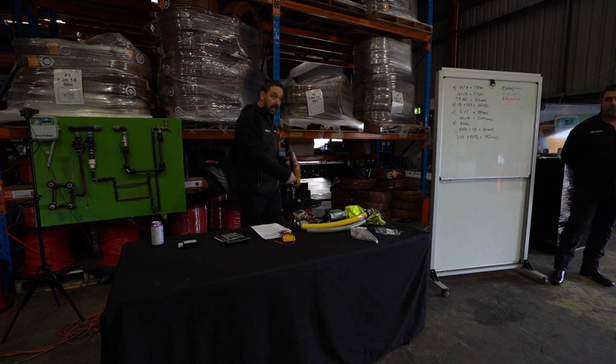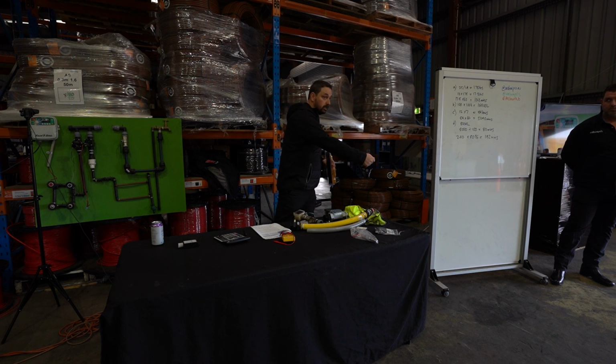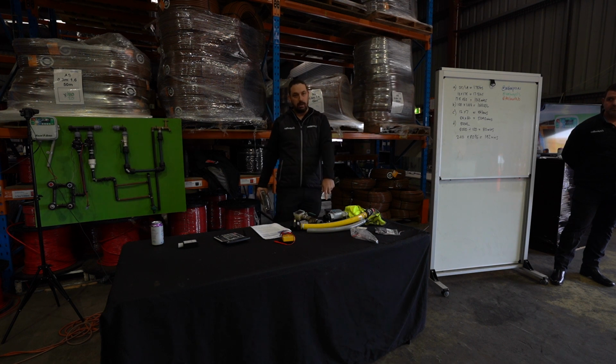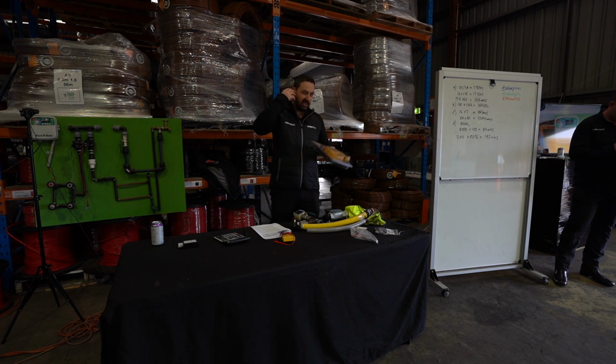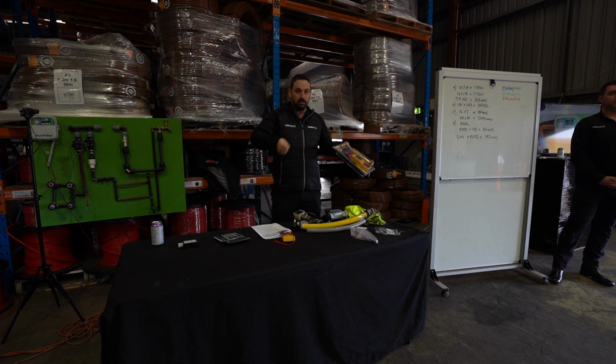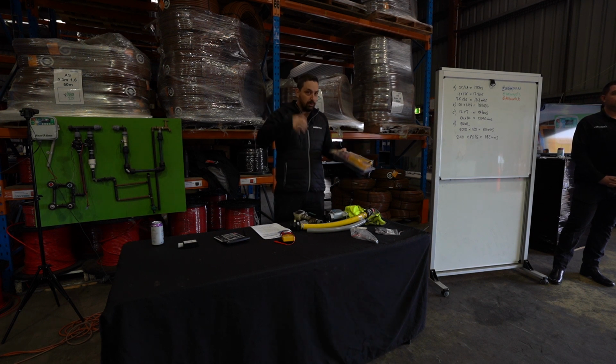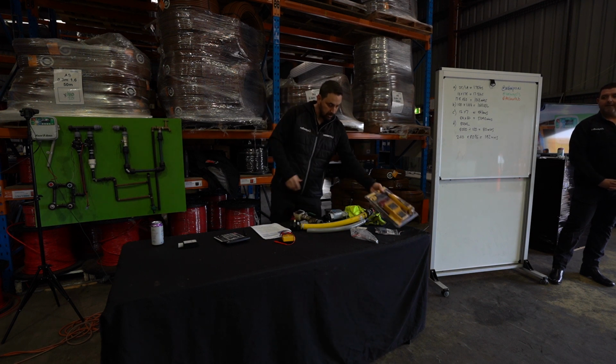and then I'd be able to walk along, and I would find the cable until I lost signal, because I might be dead out in an area, and then I'd come back and I'd find it, spray paint or dig a hole, and I'd know something's happened down here and there's a break in the line. And it can give you strength signals and all that sort of stuff, and you can get headphones with them, so if you're in a streetscape where there's cars going past, you can actually hear what's going on. So all different options.